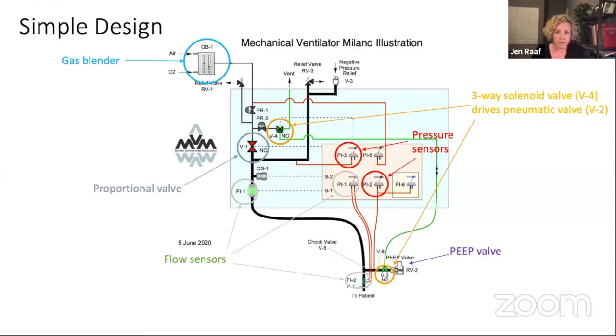Finally, this valve at the end labeled as PEEP valve is a mechanical relief valve at the end of the expiratory line, and that sets the minimum pressure left in the lungs after exhaling. Tanaz will talk a little bit more about that.